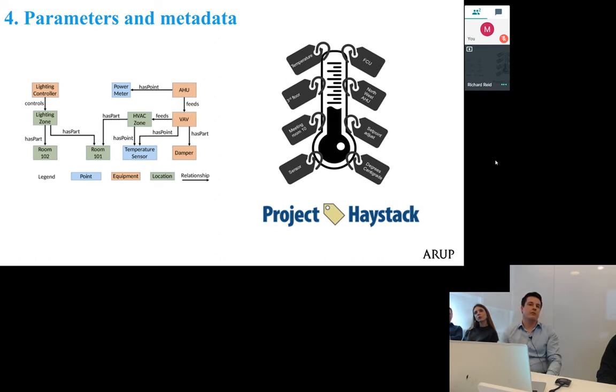On the left is what's called a graph, and this is how you link information together. So that temperature sensor is associated with the VAV in the room. That VAV is associated with the air handling unit, and it's associated with the power meter. That temperature sensor is also part of room 101. And if I had a PIR on the lighting system in room 101, then I could start to switch on the air handling unit and the terminal units based on my association with the PIR on the lighting system. So this is how we link data together to get interoperability between systems without having to physically connect them with wires, and why we can stick with those vertical silos that I talked about earlier.